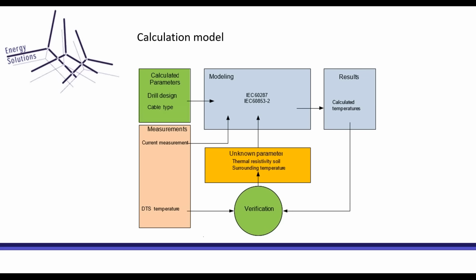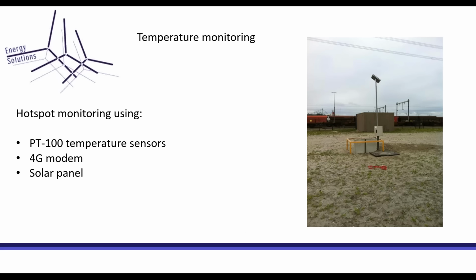But one of the very important parameters to have is the measurement data from the temperatures. With older cables, there's no temperature sensor installed. So what you can do is install, at a hotspot, a measurement pole with temperature sensors on the cable. So you need to dig up the cable, place the temperature sensors, and install the measurement pole. This is just an example using a 4G modem and a solar panel. So it's operating by itself and sending the data to a server where all the calculations are performed.